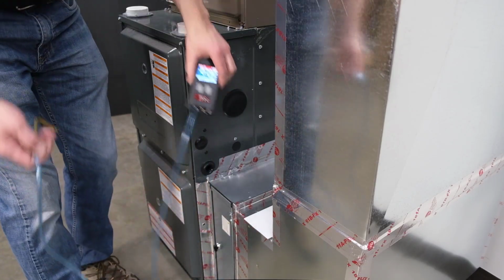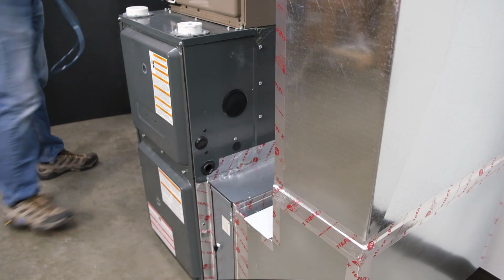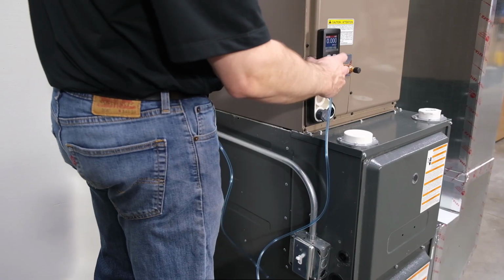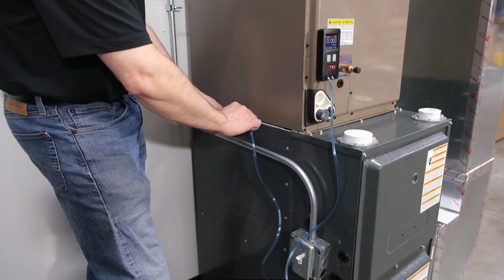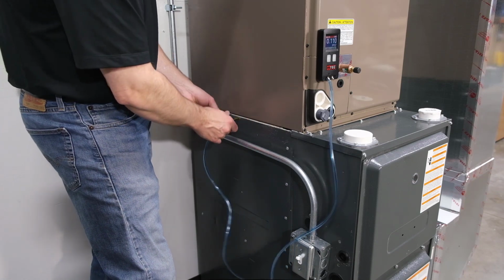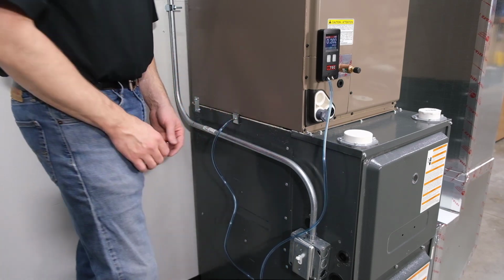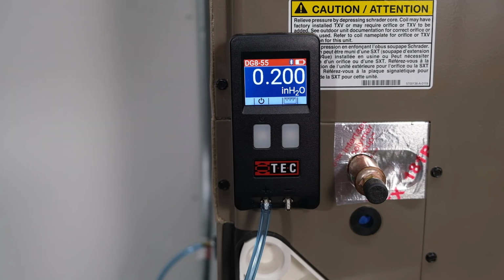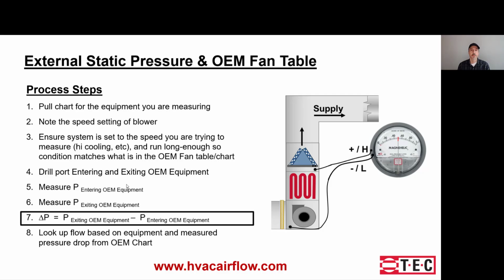Now we move over to the exit, or just before the coil. And in this case, we get about 0.2 inches. Okay, with those measurements made, we're now ready to go back to that OEM fan table or fan chart and convert our readings into flow.